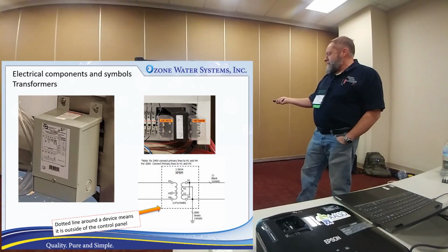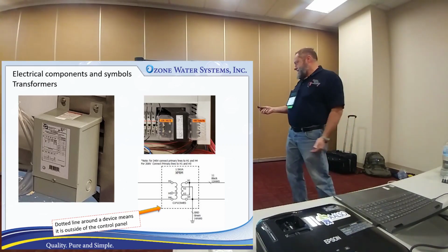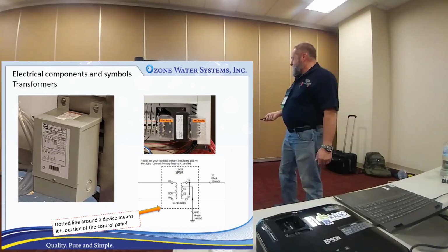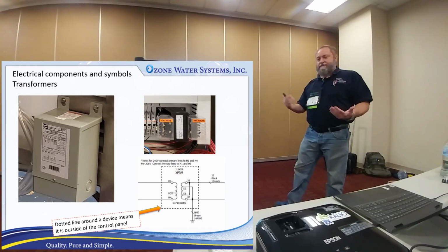We'll always have a couple of coils. They'll look different depending on the transformer layout. This particular one has different taps for different voltages if you're running at 240 volts versus 208, so that you always get the voltage output you want if your mains voltage is slightly different.